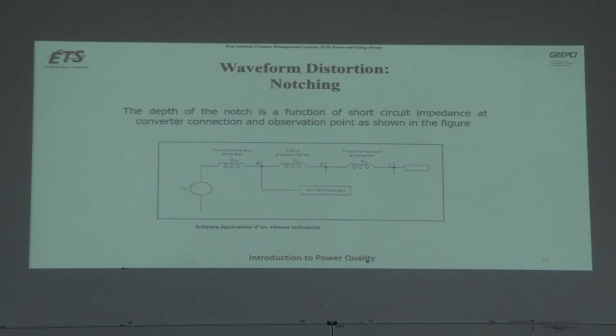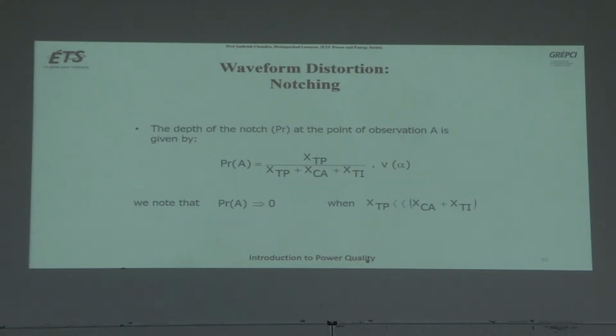Depth of the notch: you see this is the load, this is the source, and this is the principal transformer. This is the reactance of the principal transformer, this is the reactance of the cable, and this is the reactance of the isolation transformer. If you see this point of observation from here, you can see the depth of the notch is equal to the reactance of the principal transformer plus the reactance of the cable plus the isolation transformer. So if you have a very low value of reactance of the principal transformer, then you can reduce the depth of the notch.